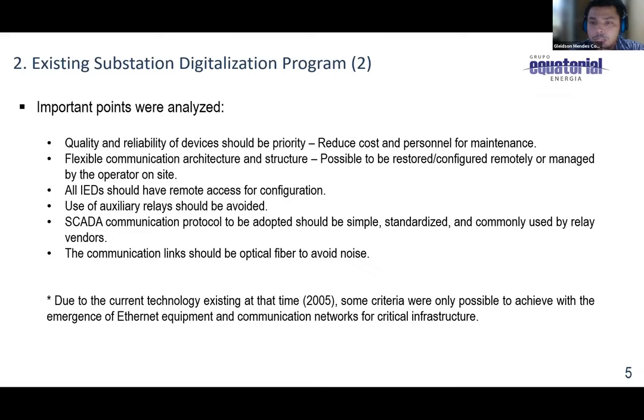Some important points that we analyzed when we started this project: quality and reliability of the device should be the priority. Due to reduced staff and expenses on the maintenance, we have to guarantee the quality of the automatic process. Flexible communication architecture and structure: it has to be possible to be restored and configured remotely, or managed by the operator on site. All the electronic devices should have remote access for configuration. So we should have access whether we are inside the substation or outside the substation. It wouldn't be a problem.